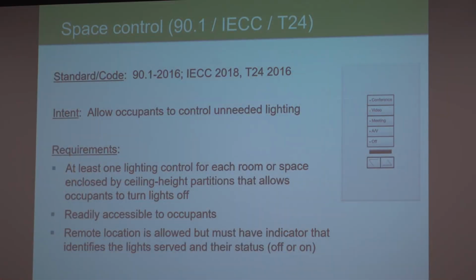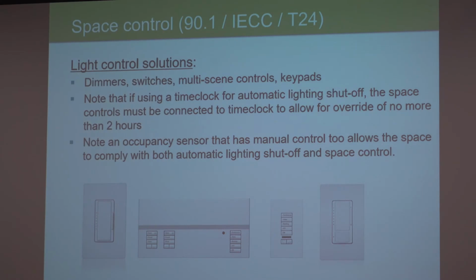Okay, so there's also requirements for area control or space control. So every room or every space inside the building has to have a lighting control, okay, to allow occupants to manually turn off the lights. That's the gist of it, okay? So you have to have one control in each room. It has to be readily accessible. You can have it in a remote location as long as there's an indicator that identifies the lights that are being served by the control. Basically, all manual lighting controls comply with space control. It could be a regular switch, it could be a dimmer, it could be a scene control, it could be a keypad.